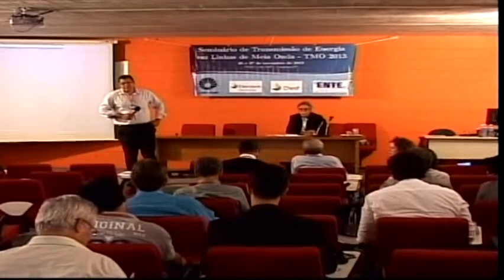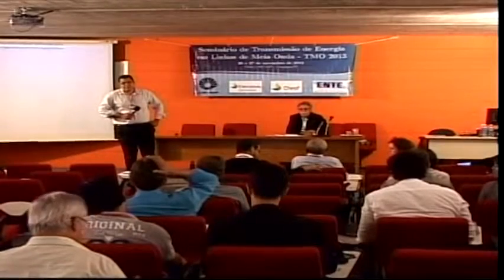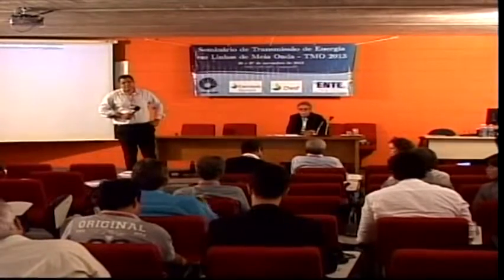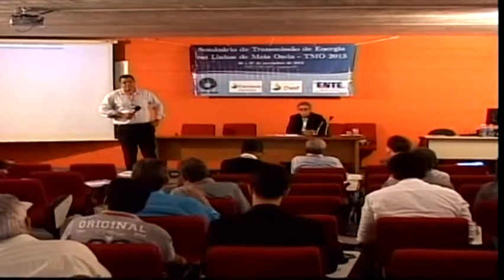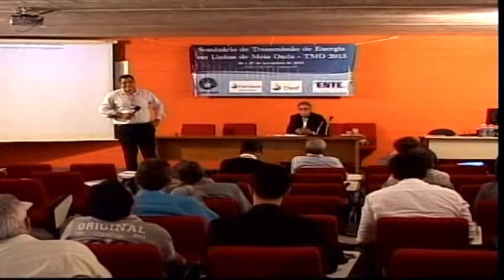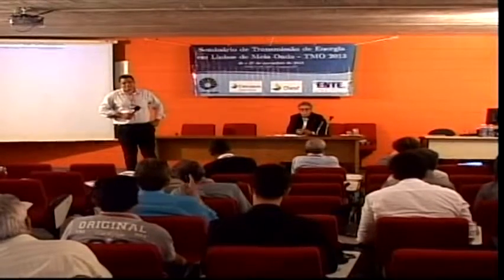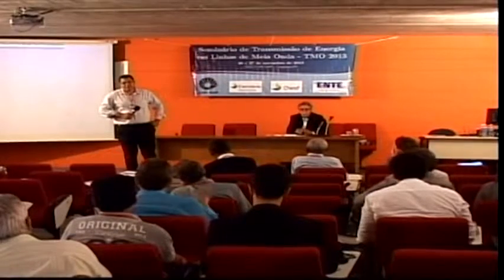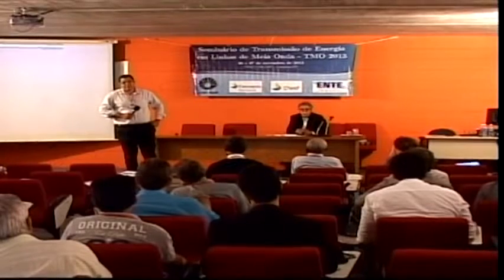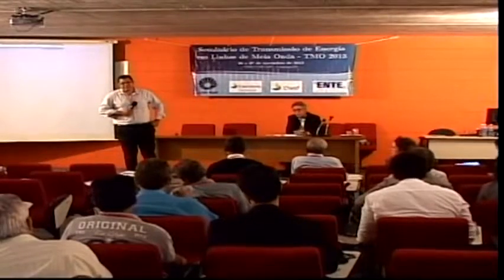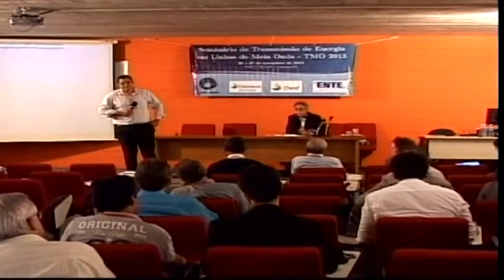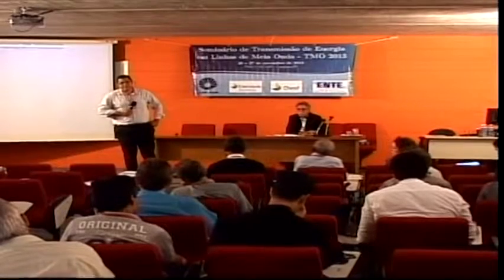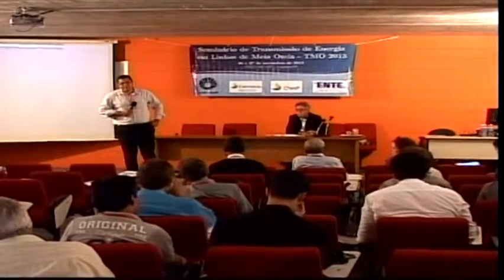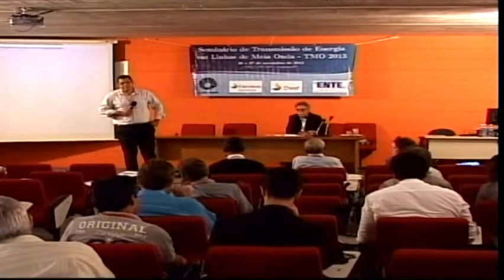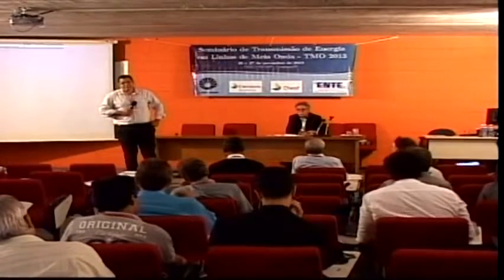Professor, the purpose of your simulations, from what I have understood, is to verify the maximum demands on the generator or generators in Serra da Mesa, both overvoltage and overcurrent demands. The representation used for the machine, I understood, was the Model 4, everything complete, and you had the opportunity to include the voltage regulator. So my first question, more out of curiosity, is: up until the 30 cycles or 500 milliseconds, what was the influence, if you detect any, of the presence of the voltage regulator?